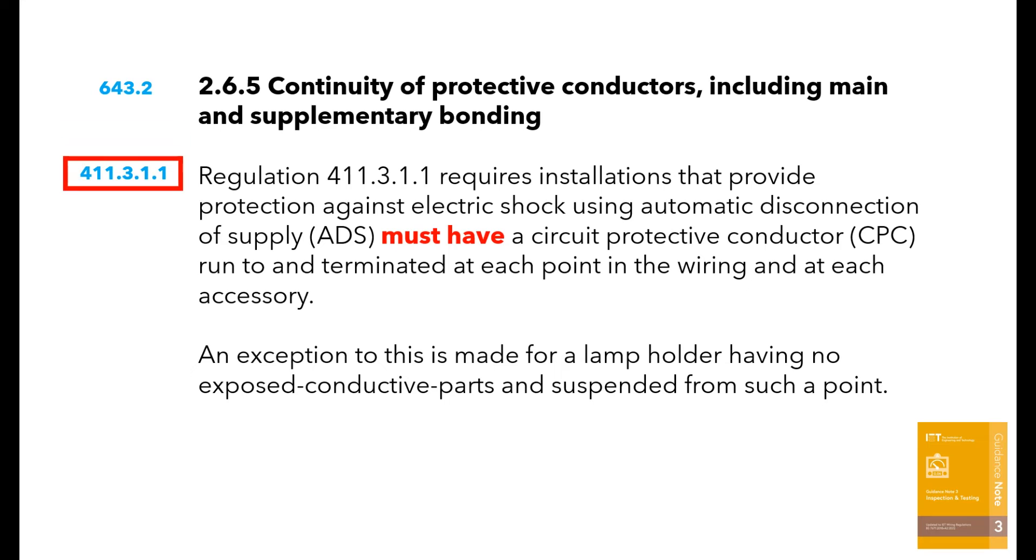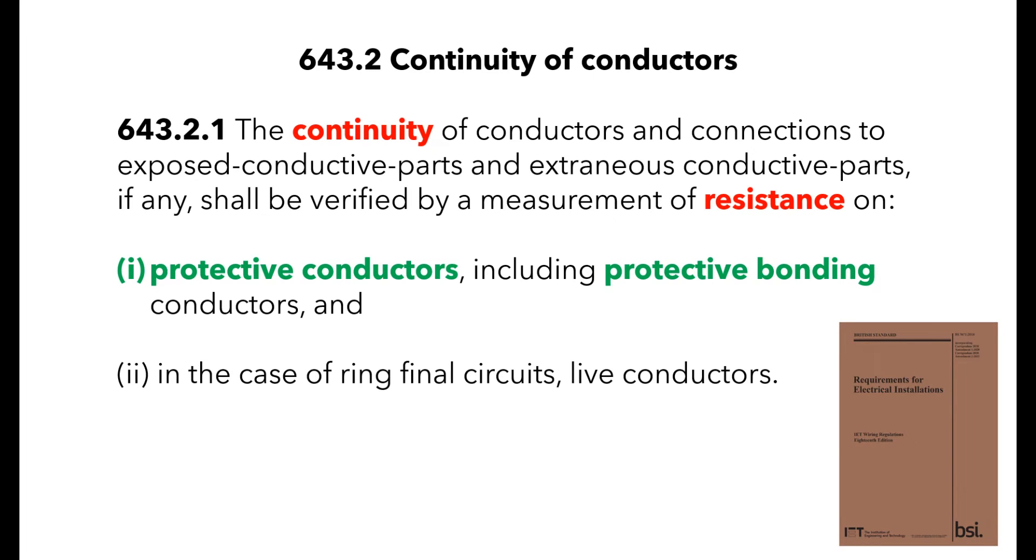Effectively, Regulation 411.3.1.1 requires that a circuit using ADS, automatic disconnection of the supply, as its protection against electric shock must have a circuit protective conductor, CPC, run to each point in the wiring and at each accessory. There is an exception to this rule for a lamp holder having no exposed conductive parts and being suspended from such a point, like our humble friend the plastic ceiling rose. This references Regulation 643.2, which states continuity of conductors and connections to exposed conductive parts and extraneous conductive parts needs to be verified by measuring its resistance and proving that it is continuous.